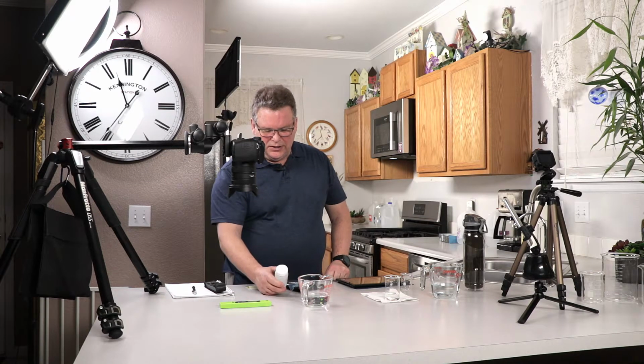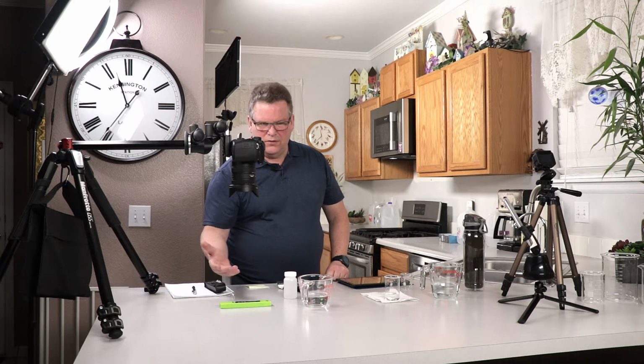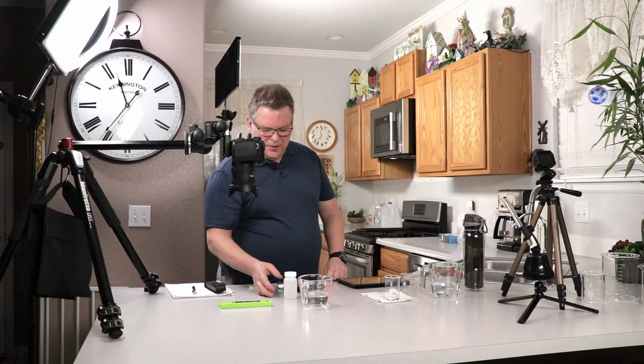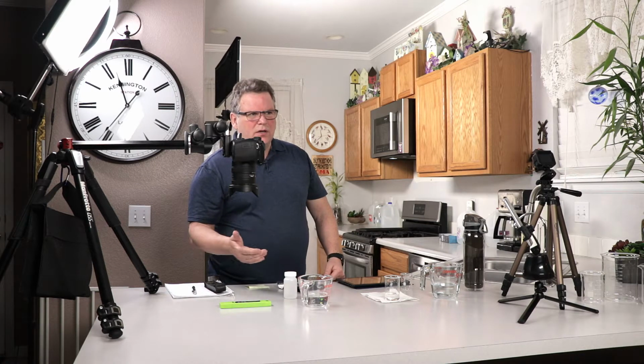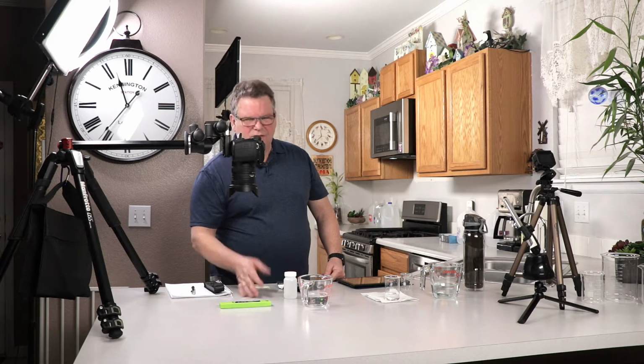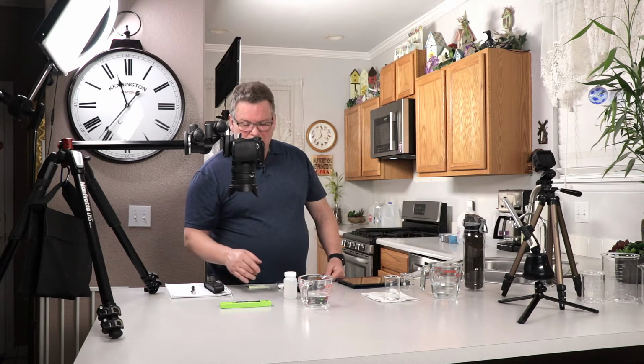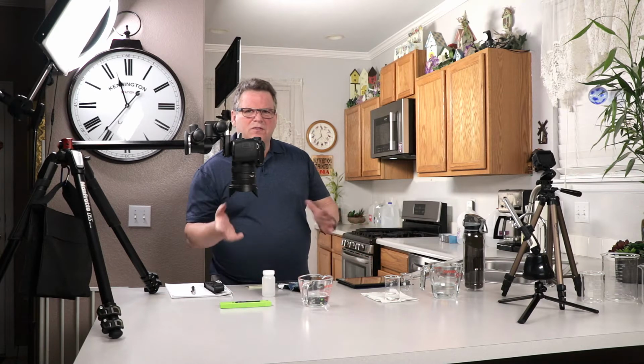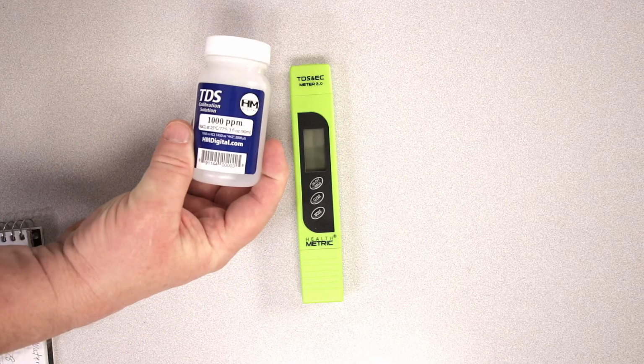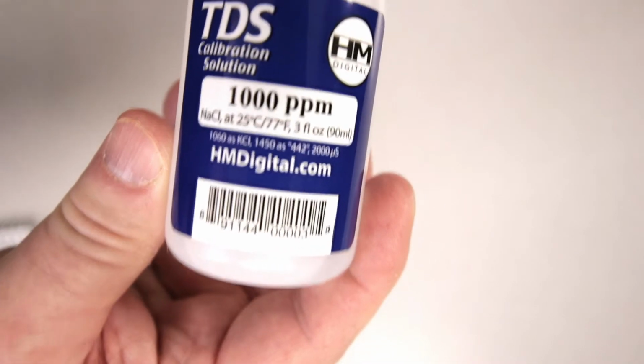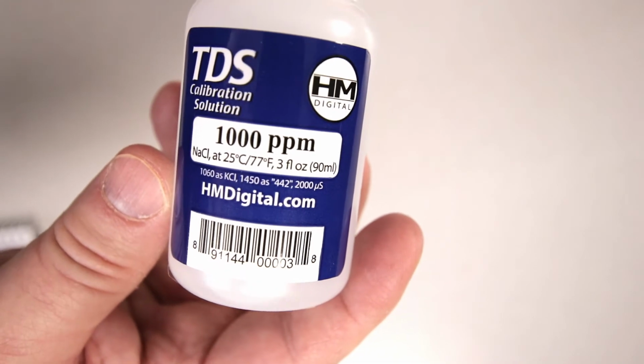One of the things that you can do is it comes out of the manufacturer with 300 parts per million TDS, but you may live in an area of the country that exceeds that and actually gets into 1,000 parts per million TDS, and that's a boil advisory at that point. So you don't want to calibrate with something that's lower. You want to get something that's a little higher up. Just for your benefit, I just wanted to show that they actually make 1,000 parts per million calibration solution. So 1,000 ppms. I think this cost a few bucks to get.